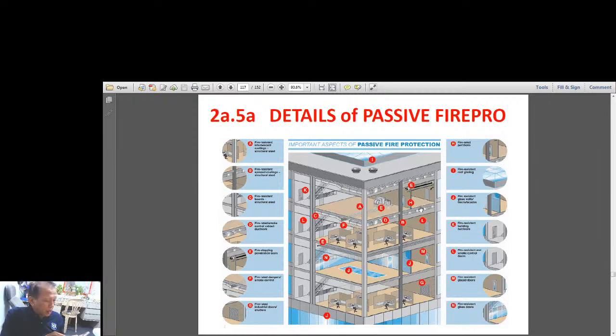Yuri Taraki, 2 weeks ago, our Novec 1230 was activated by a false alarm. 2 cylinders were empty for only 10 minutes. We replaced them with new tanks. We found out that the false alarm was caused by dust due to a sandstorm. Oh, so meaning to say you had a sandstorm there and the dust came in and it was detected by your detectors. It was assuming that it was a smoke, or a fire or a smoke, and then it actuated your Novec. So there's something.